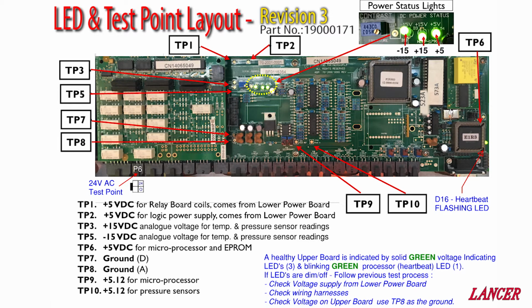LEDs indicate a healthy DC supply voltage. From left to right, the LEDs are negative 15 volts, positive 15 volts, and positive 5 volt DC. 15 volts DC is used to provide voltage to pressure and temperature sensors. 5 volts DC is used to supply the relay board coils and the logic processors. The next key indicator of a healthy upper board is the flashing LED on the far right hand side. This is the heartbeat LED indicator. This means that the processor and the program are functioning correctly.